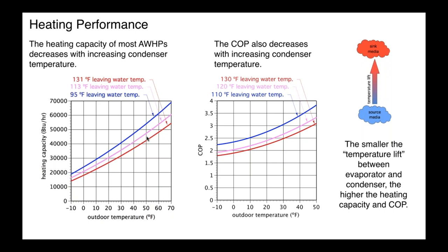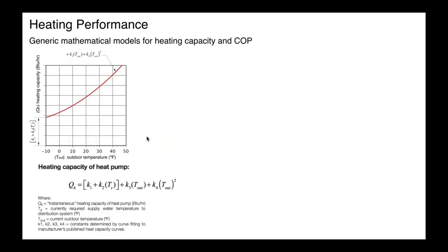So it is very important, as Bob was saying, don't just cut out a boiler from, for example, a baseboard system and drop a heat pump in and expect that that's going to be a workable system. You've got to make sure that the balance of the system, everything but the heat pump, is compatible with low water temperature operation to get a good performing system.